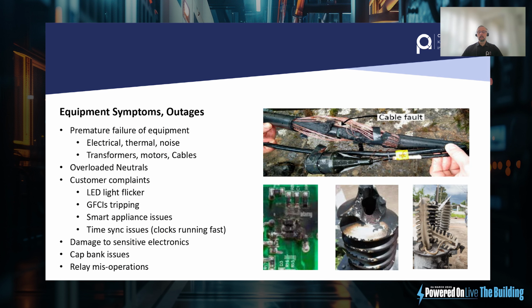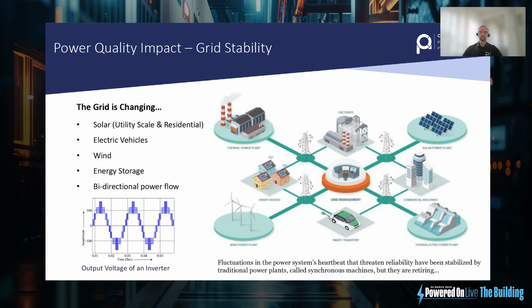Some of the symptoms if we don't look after power quality are overheating, degrading of components, and premature failure of equipment. Maybe the product's longevity is designed to last 7 to 10 years, maybe 10 to 15 years is the design life of the hardware, but it's failing in 3 years, 4 years, maybe even in the first year. It depends. There's a whole host of reasons for that, but most of them are related to power quality.